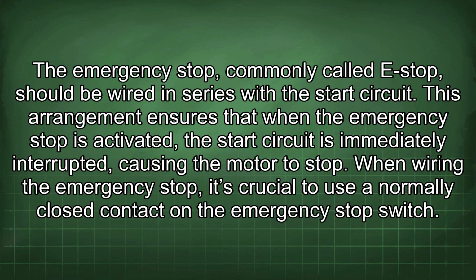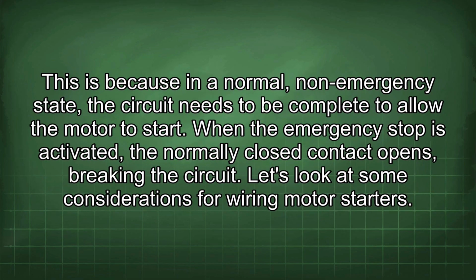The emergency stop, commonly called e-stop, should be wired in series with the start circuit. This arrangement ensures that when the emergency stop is activated, the start circuit is immediately interrupted, causing the motor to stop. When wiring the emergency stop, it's crucial to use a normally closed contact on the emergency stop switch. This is because in a normal, non-emergency state, the circuit needs to be complete to allow the motor to start. When the emergency stop is activated, the normally closed contact opens, breaking the circuit.